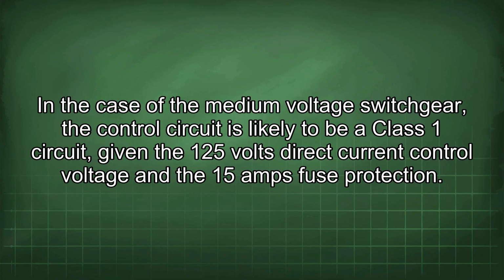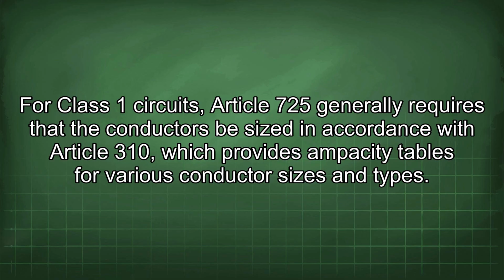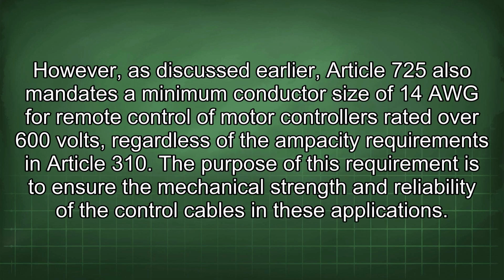In the case of the medium voltage switchgear, the control circuit is likely to be a Class 1 circuit, given the 125 volts direct current control voltage and the 15 amps fuse protection. For Class 1 circuits, Article 725 generally requires that the conductors be sized in accordance with Article 310, which provides ampacity tables for various conductor sizes and types. However, as discussed earlier, Article 725 also mandates a minimum conductor size of 14 AWG for remote control of motor controllers rated over 600 volts, regardless of the ampacity requirements in Article 310. The purpose of this requirement is to ensure the mechanical strength and reliability of the control cables in these applications.